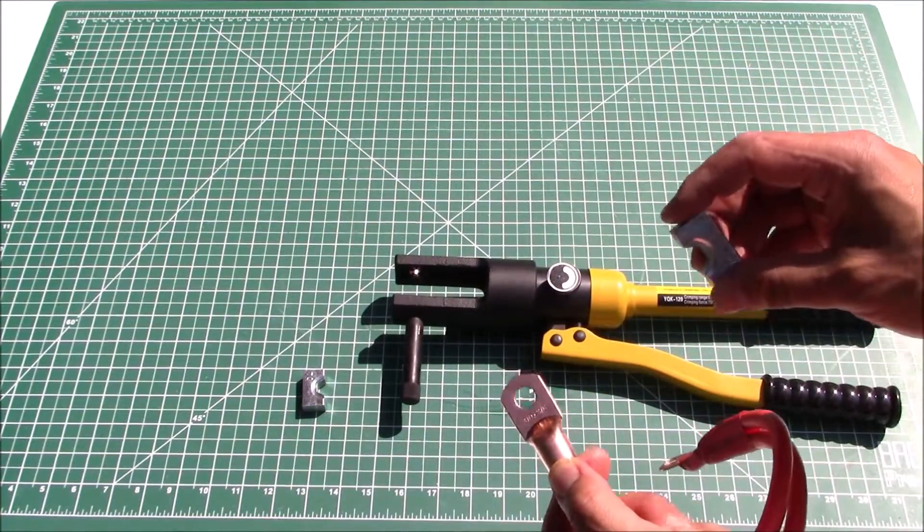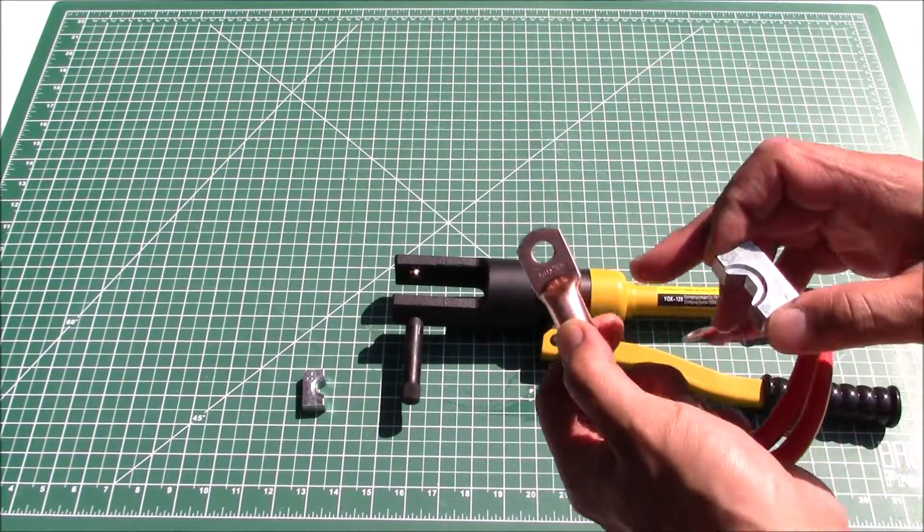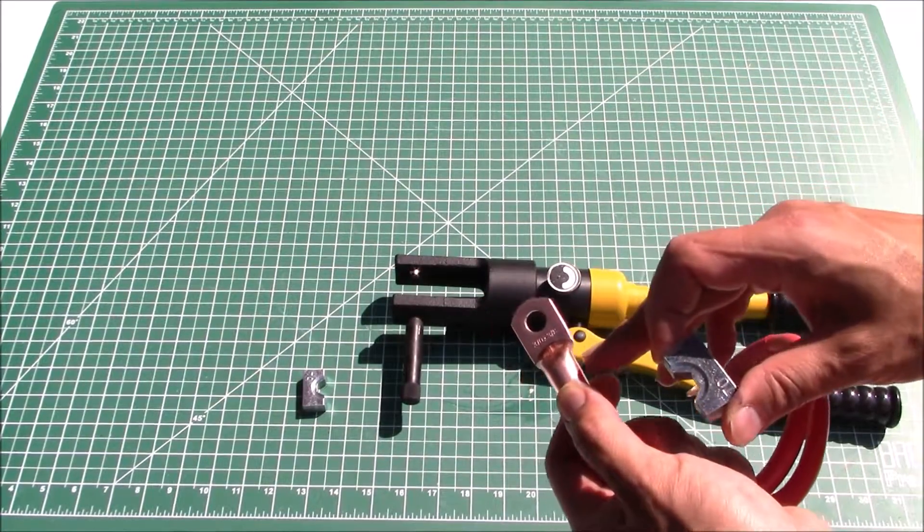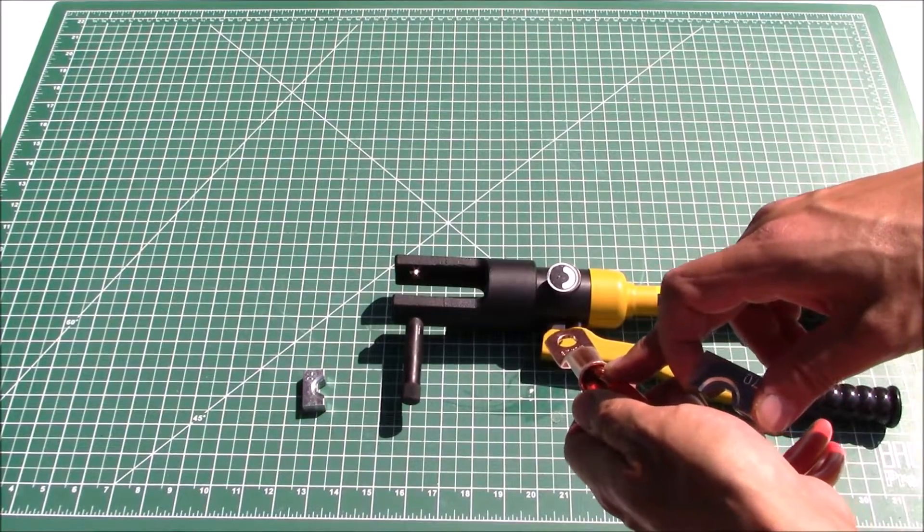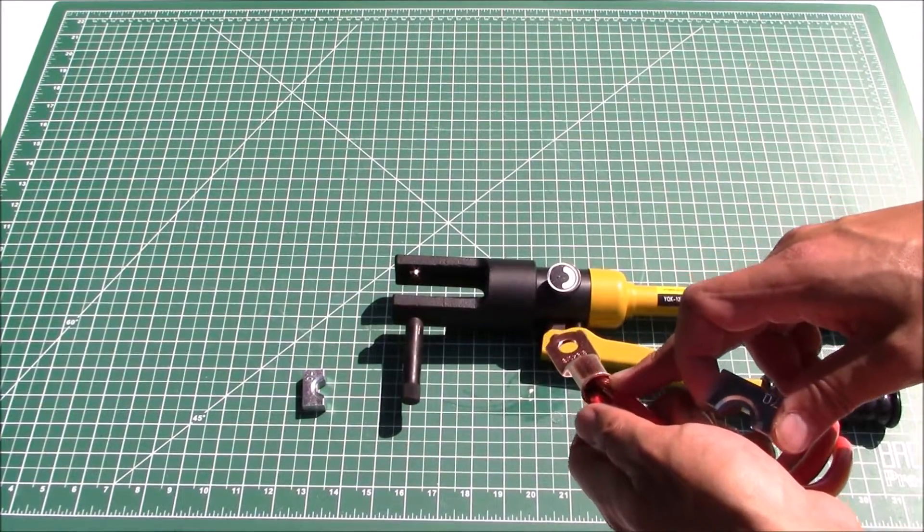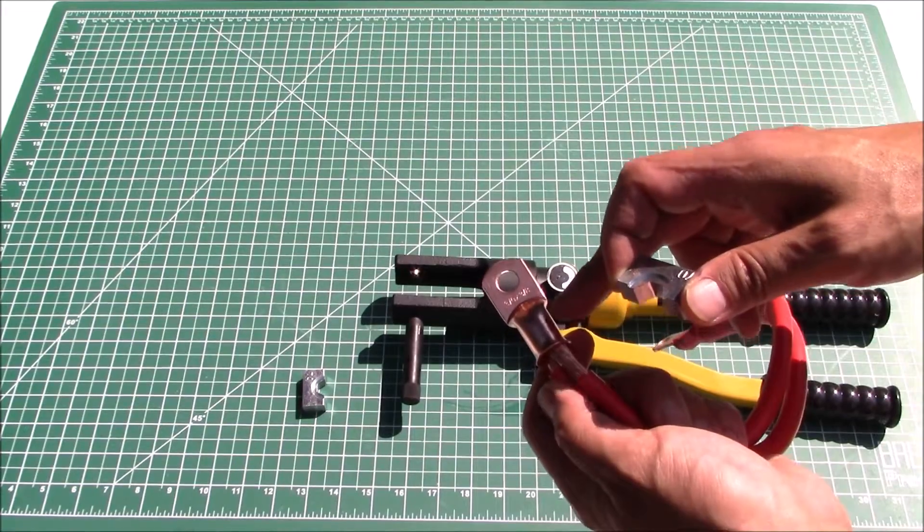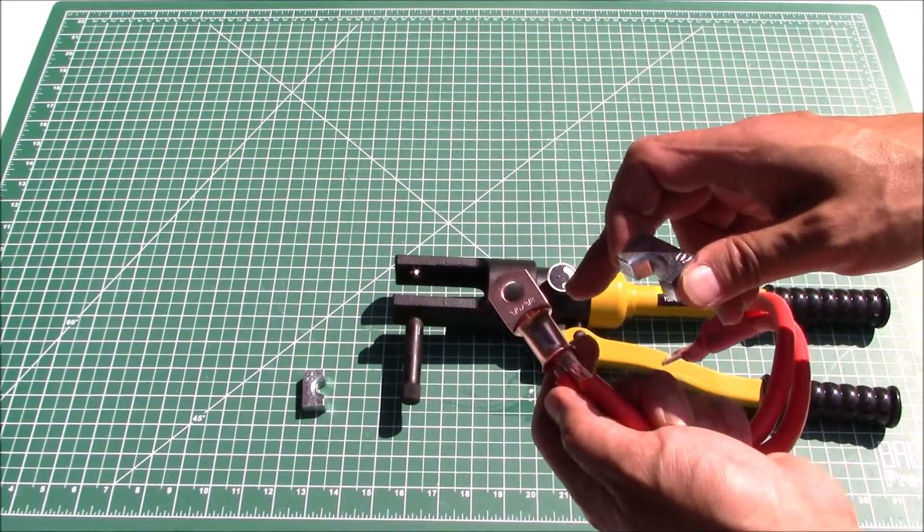In this case I'm going to use these dies which are actually a tiny bit smaller than advertised or spec, but again that's because the wire inside is a little bit smaller than it's supposed to be. So I'm going to need to crush this lug or crimp this lug a little bit tighter than necessary.